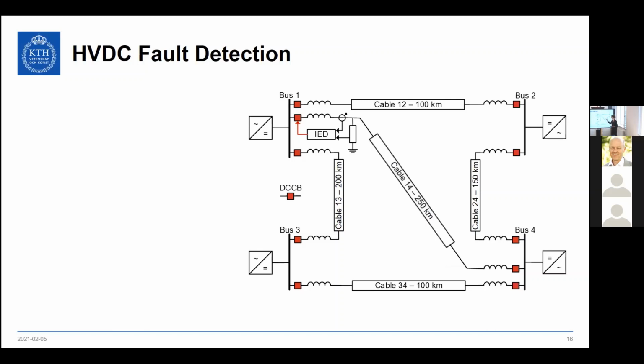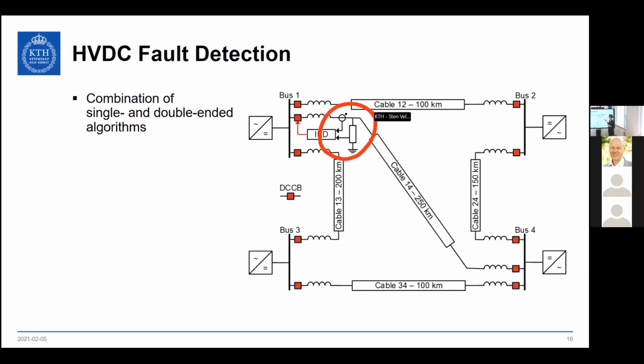But going back to the actual IED and what it's doing. So inside of this IED, there's a mathematical equation working that's called fault detection algorithm. And fault detection algorithms in this context can be distinguished into single and double-ended algorithms. So what is shown here is a single-ended fault detection because it only looks at local measurements. And if instead this IED had another input with communication and information coming from a remote line-end IED, then you would call this a double-ended fault detection.